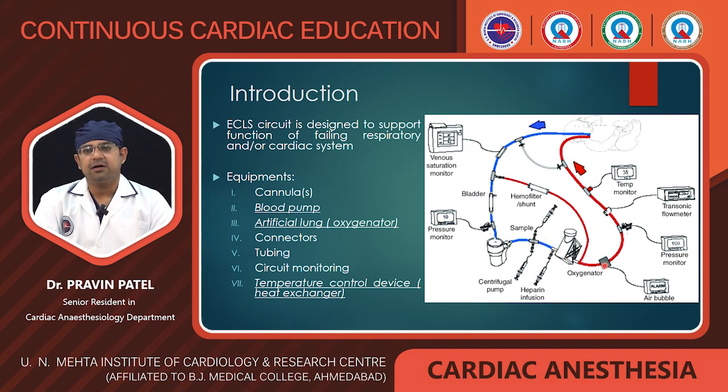After that comes the air bubble detector. This is basically to prevent air embolism. Then comes the second pressure monitor. This is to monitor the pressure of the return cannula. Then comes the temperature monitor. Again it measures the temperature, the output temperature to the patient. So these are all the additional connections which make the circuit complex.